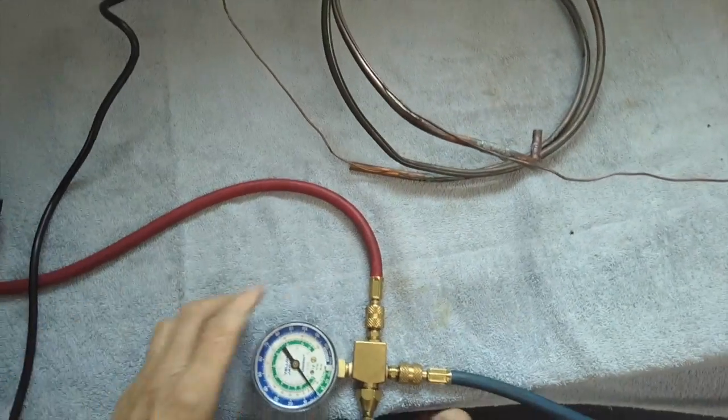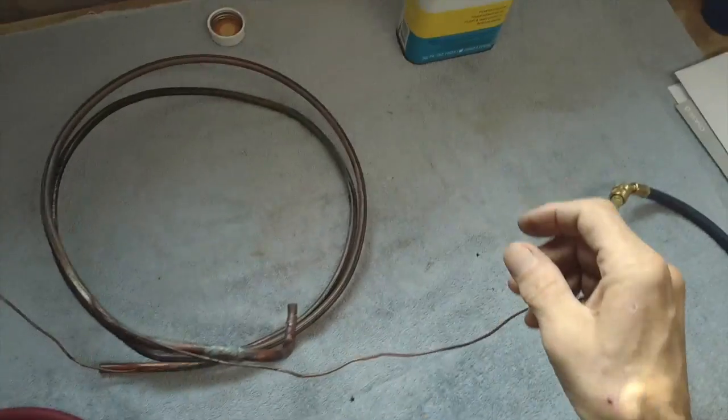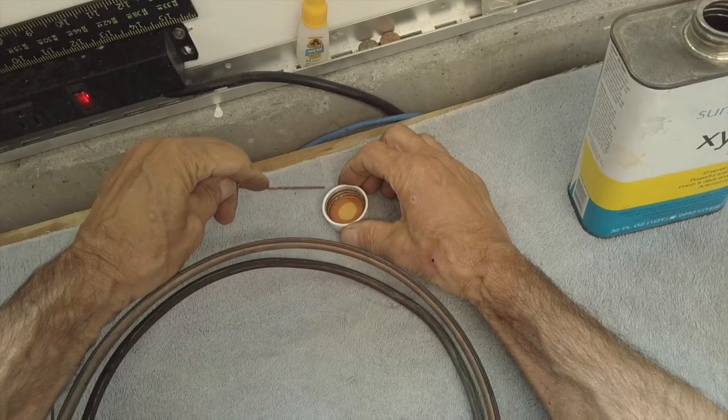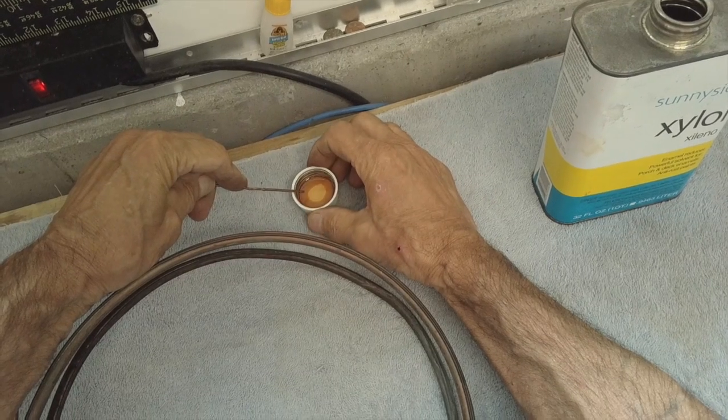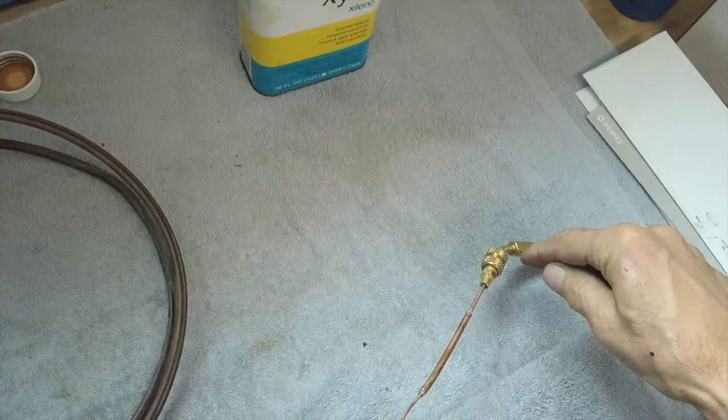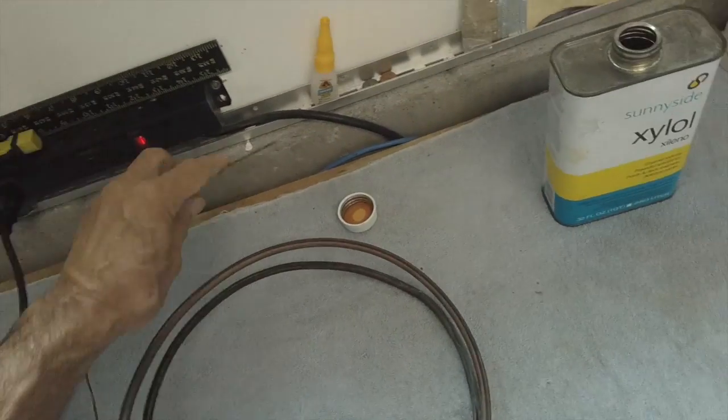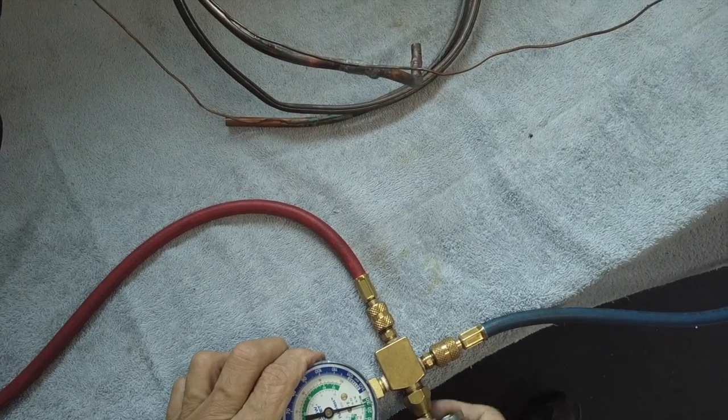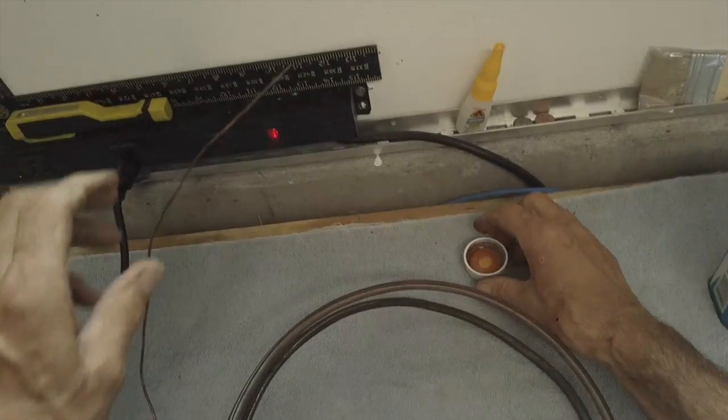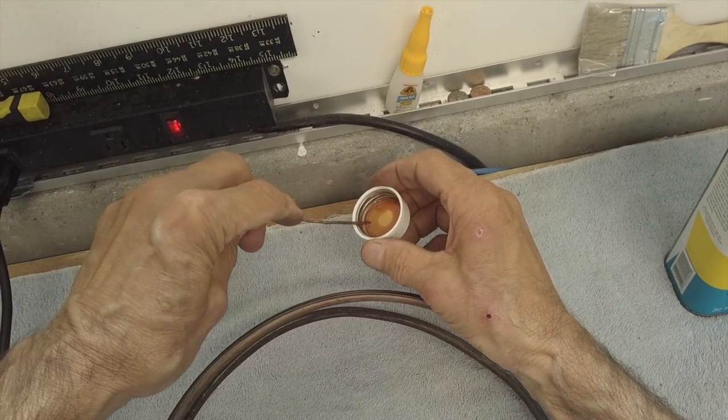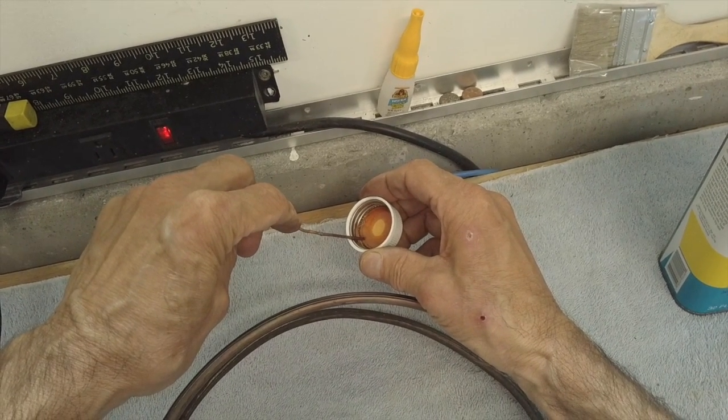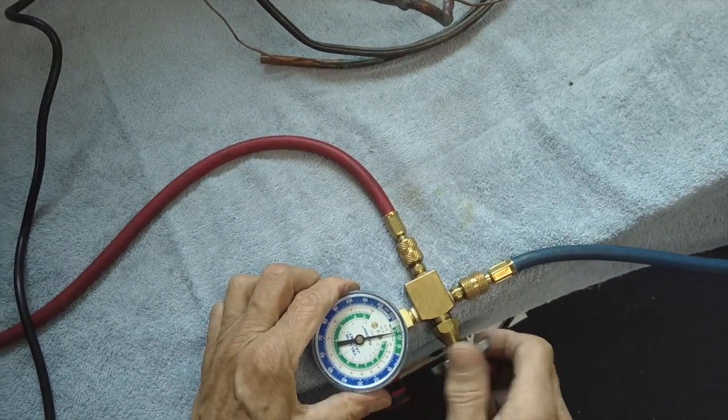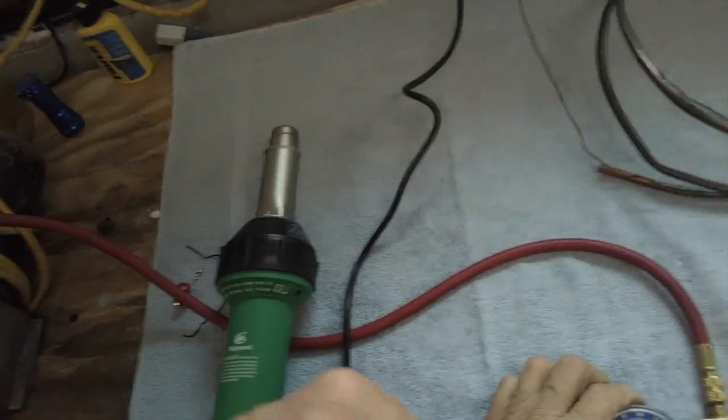What we're going to do here is we're going to use a little bit of enamel reducer. Notice I put it in this little cap, and we're going to put the capillary tube into the enamel reducer and let it flush through and clean out the pipe and come out through here. There's not really enough in the cap to fill the tube, but it'll flush it through. So we'll open up the gauge, pull the vacuum, and we'll know if this is clear because it will suck out that enamel reducer. You can see it's going in. So immediately, we will shut off the gauge.